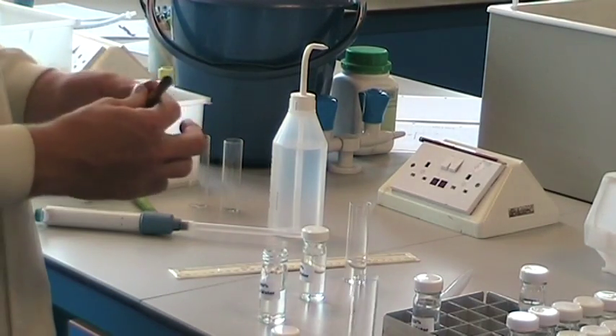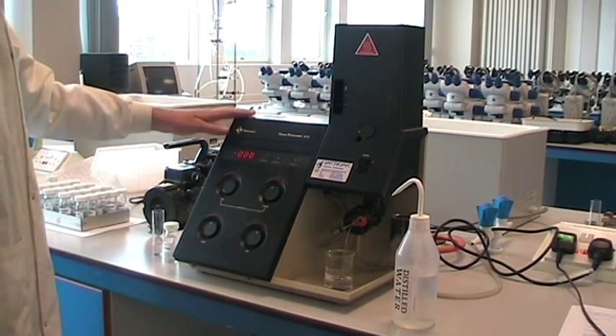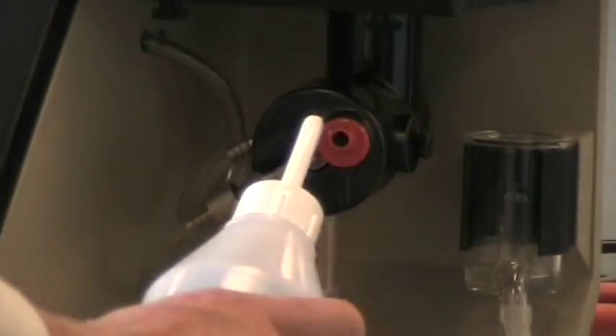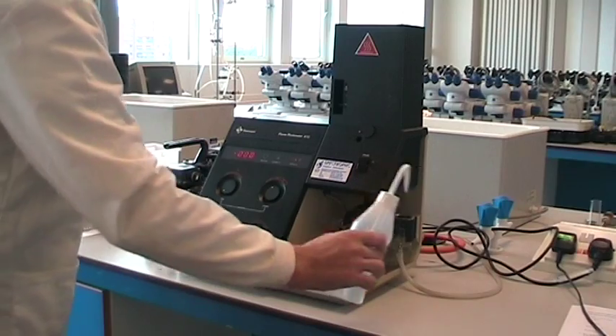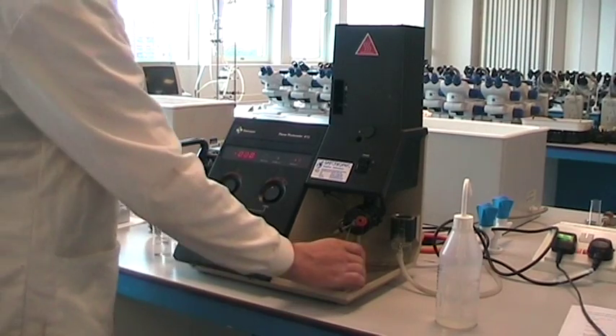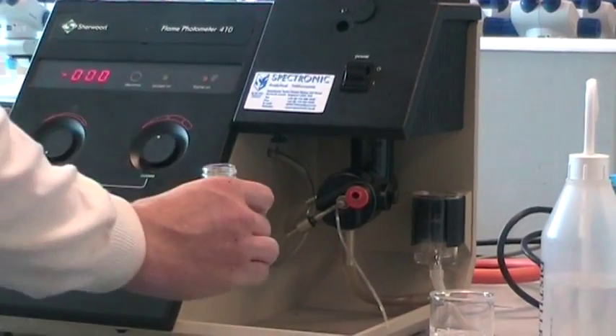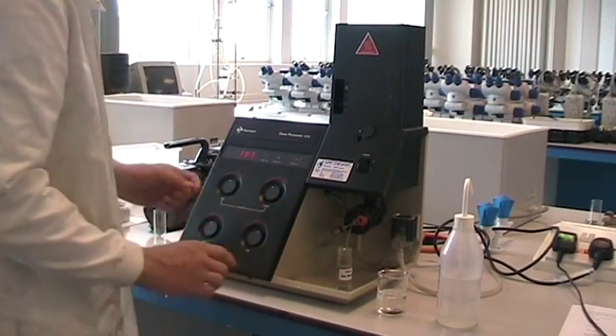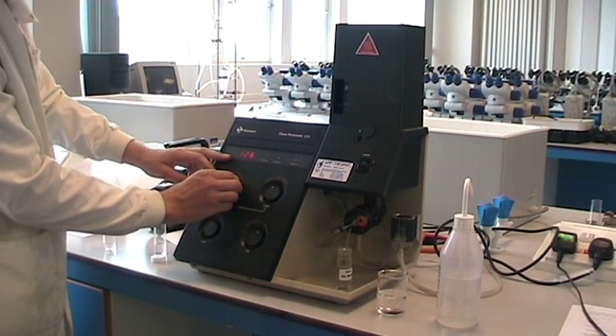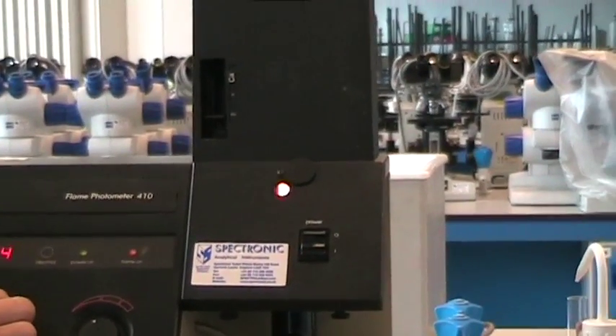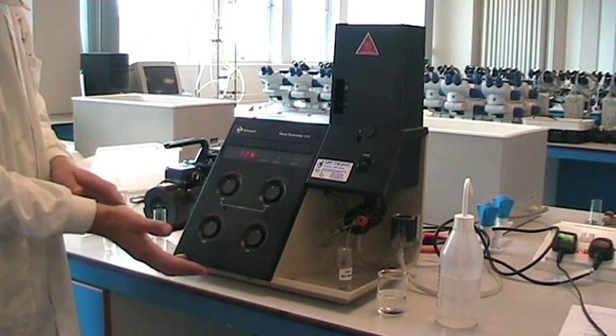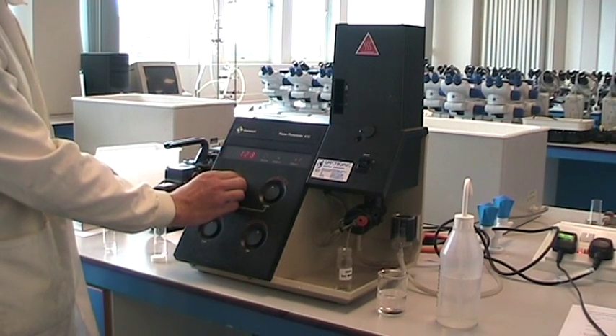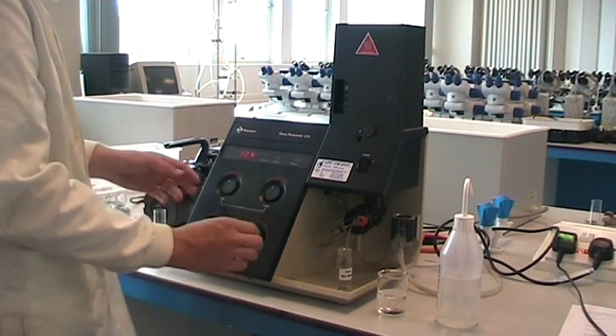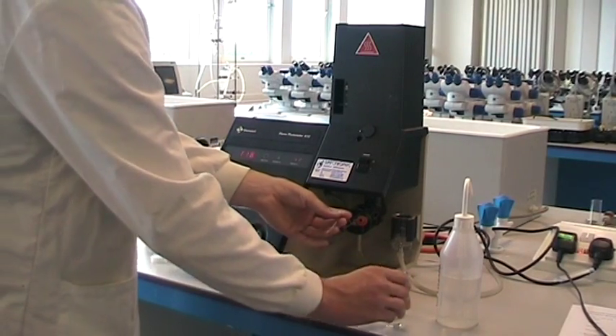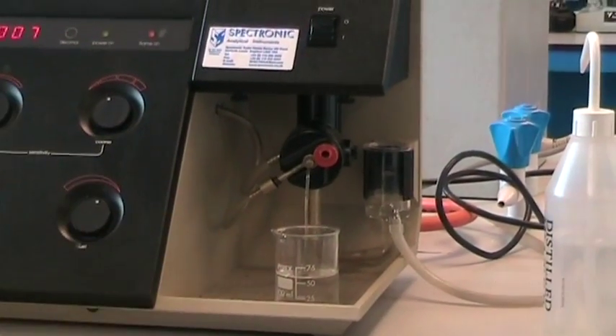This is a flame photometer. It's set to measure sodium ion concentration. It sucks water up through this tube here, so you want to make sure that this reservoir is always full. Now, to calibrate it, we'll be using 125% seawater. Then adjust this to 125. That sets your highest parameter for sodium concentration. You then carry out the same thing with distilled water. You ensure that that is set to zero.